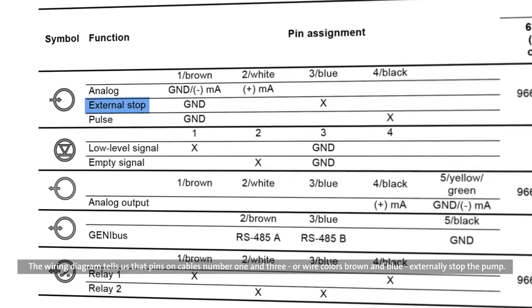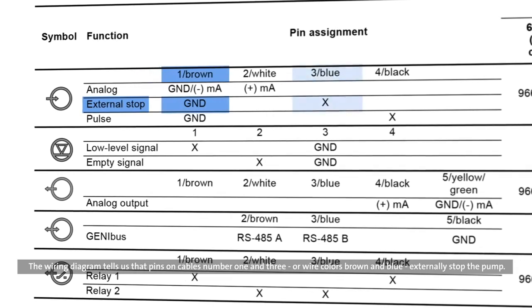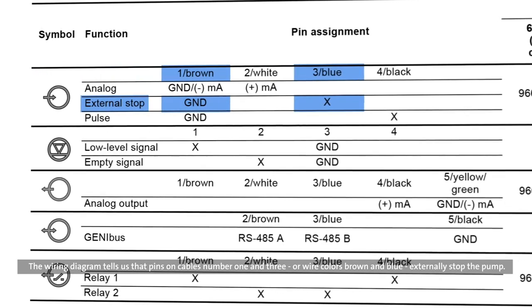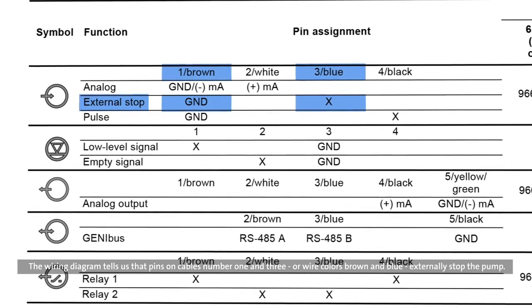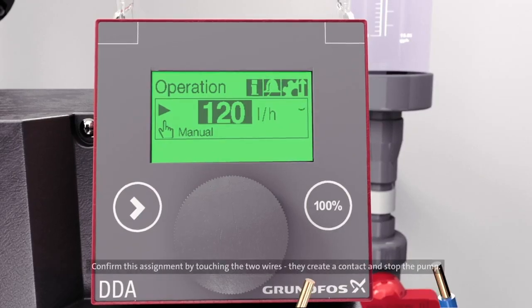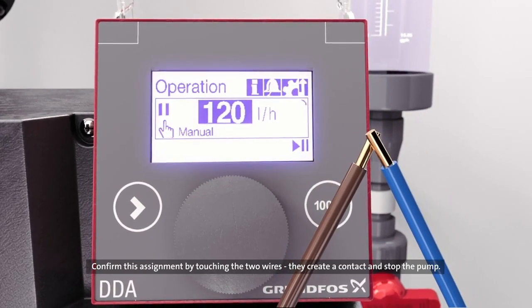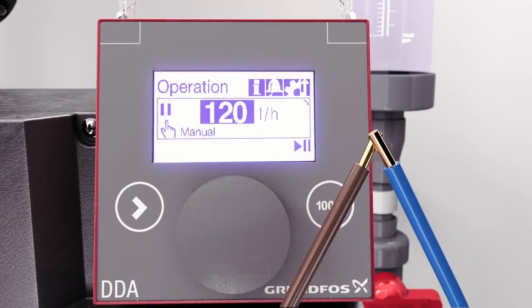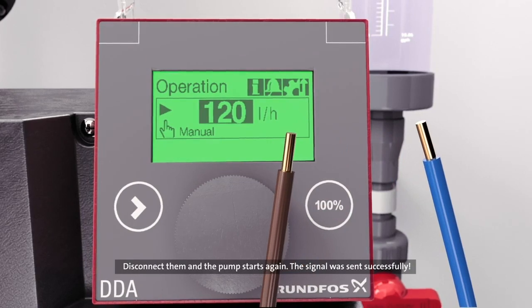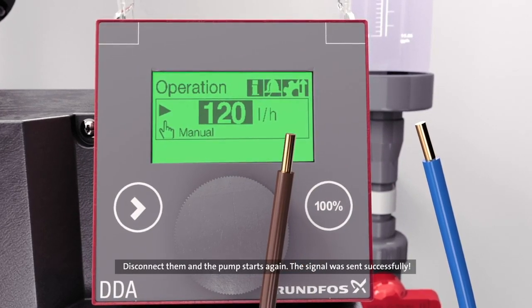The wiring diagram tells us that pins on cables number 1 and 3, or wire colors brown and blue, externally stop the pump. Confirm this assignment by touching the two wires. They create contact and stop the pump. Disconnect them and the pump starts again. The signal was sent successfully.